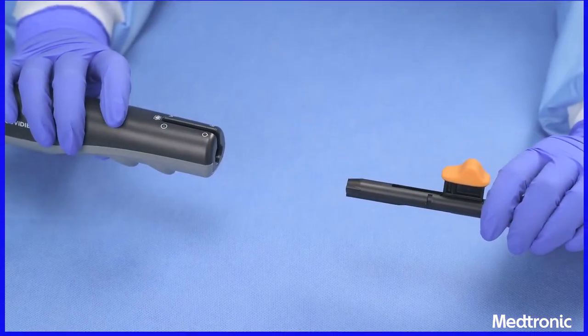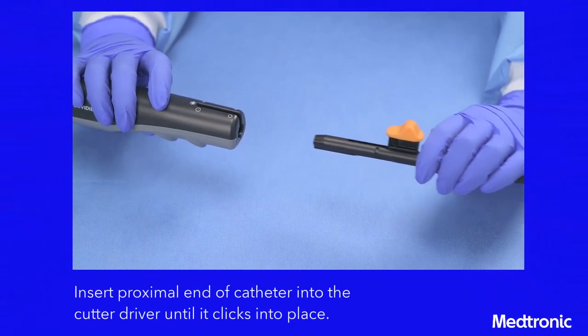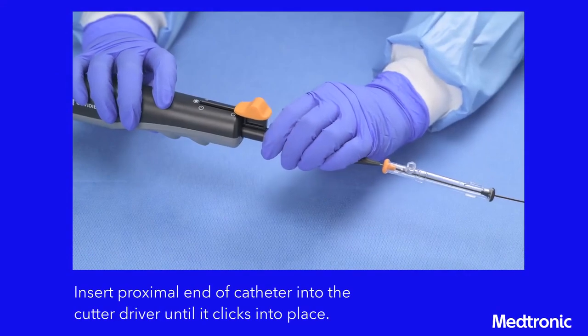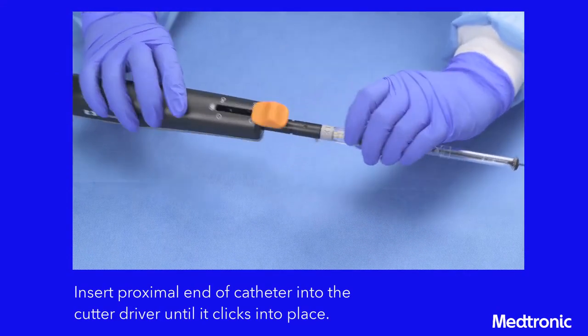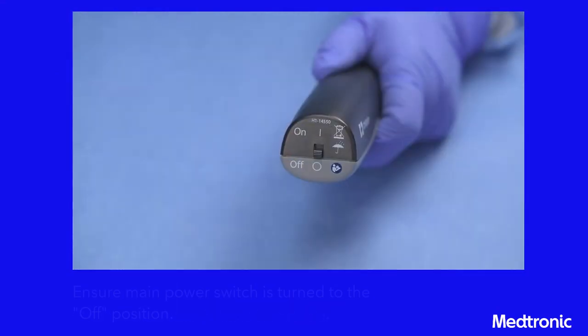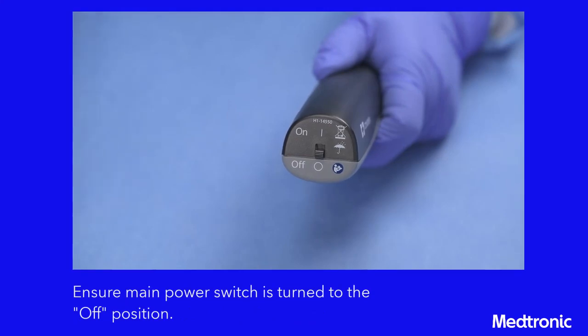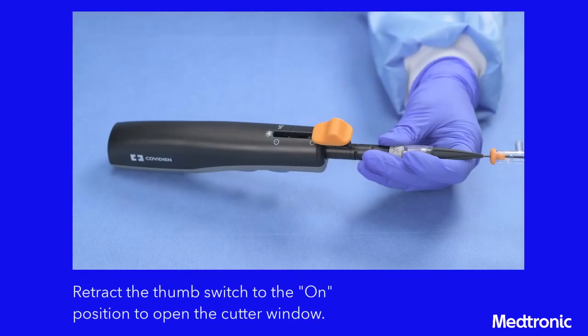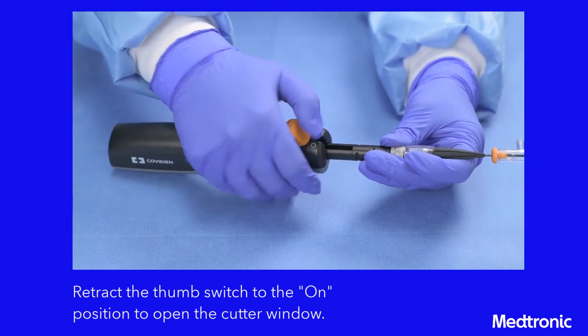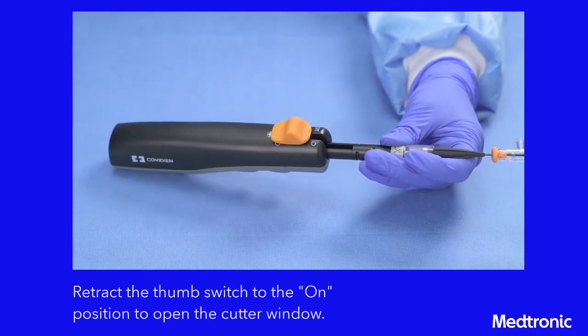Prep the device. First, insert the proximal end of the catheter into the cutter driver until it clicks into place. Next, ensure that the main power switch on the cutter driver is turned to the off position, and retract the thumb switch to the on position to open the cutter window. Now, air will be purged from the catheter.